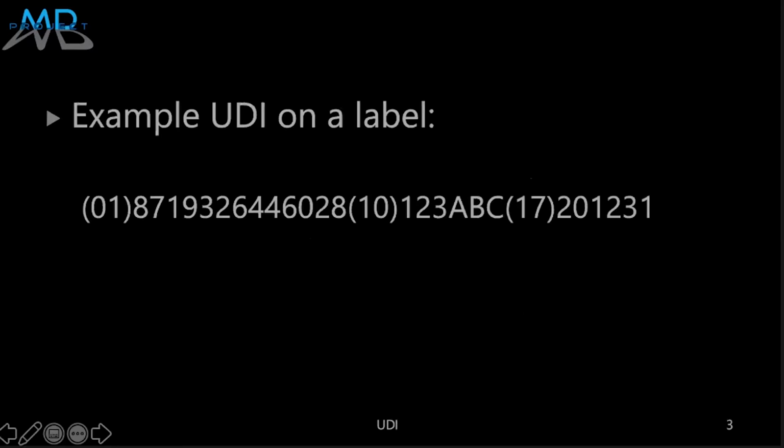So you could have 10 UDIs for the 10 pieces of equipment that your hospital buys. They will all have the same UDI DI because they all bought the same basic model, the Super MD Sterilizer 2000, but they all will have their unique serial number, and they can also have the same configuration number, which could be BTR, for example, the blue top right.